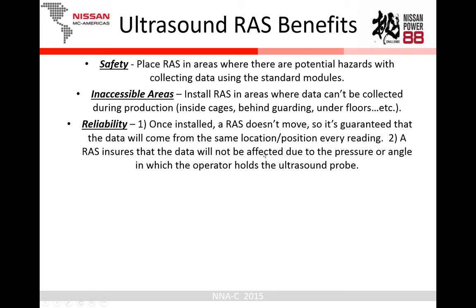A half an inch or something that might make a difference in those readings. A RAS ensures that the data will not be affected due to the pressure or angle at which an operator holds the ultrasound probe. A lot of our readings, most of them actually, we use the stethoscope, so according to how hard you press that stethoscope down, or the angle at which you hold it, could be an issue as far as getting readings go. And we like our readings to be as linear as possible without being erratic.